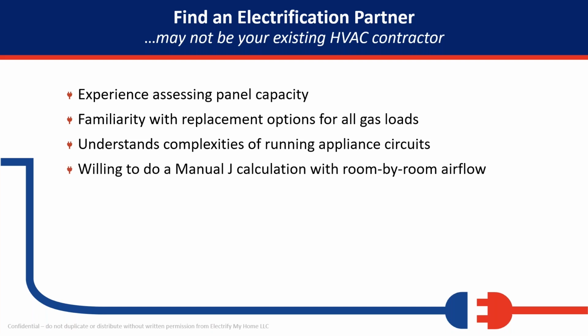For a heat pump to work optimally, we need to have the duct system designed in such a way that the airflow necessary for the capacity of each room is being delivered, because heat pumps need to run a lot longer. Longer run times can help mix the air and make the house more comfortable, but it can also exacerbate comfort problems if we're getting too much or not enough air into a room.